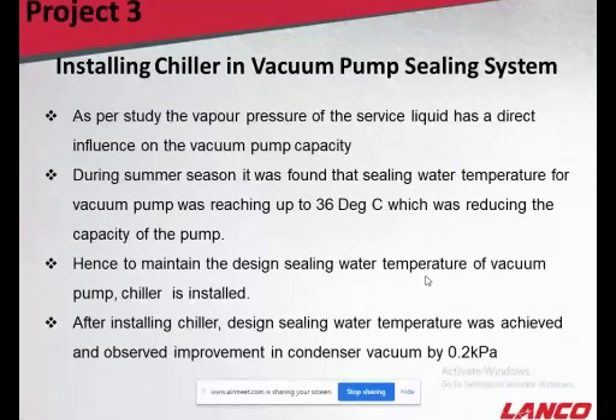The OEM also says that if there is a change in the service liquid, it has a direct influence on the vacuum pump capacity. So during summer, this temperature was reaching up to 36 degrees against the design of 32 degrees. As the temperature increased, it reduced the capacity of the pump. So the pump was not able to perform at its maximum capacity at this temperature because the sealing water temperature deviated from its design values. Hence, to maintain the design water temperature of this vacuum pump, a chiller was installed. This chiller was designed for the capacity of the sealing water flow, and the temperature was achieved as per the OEM temperature.